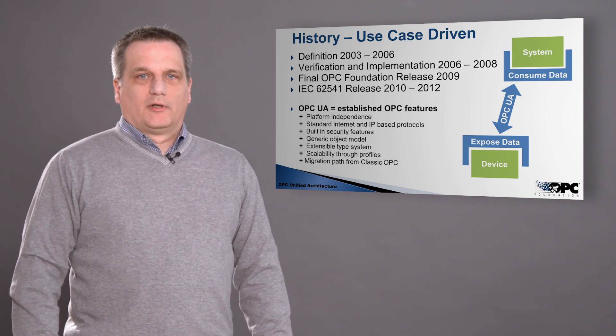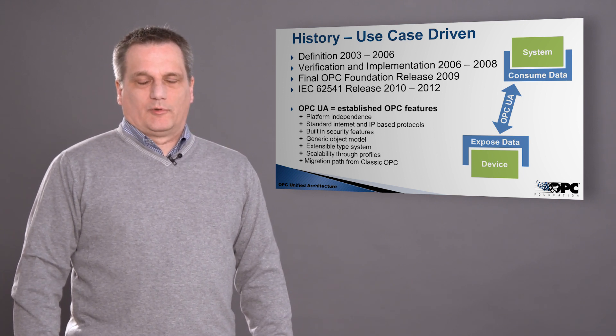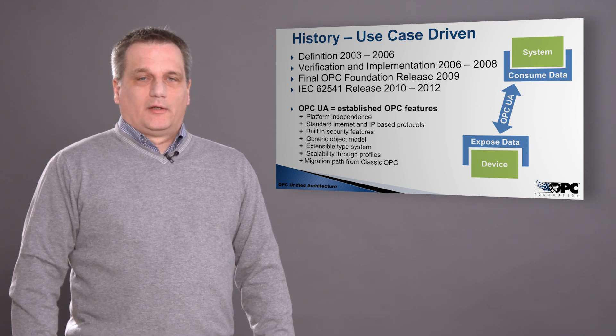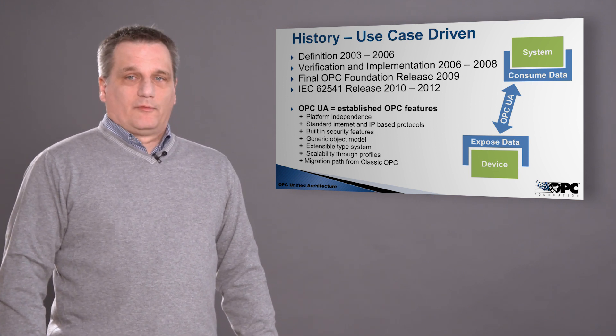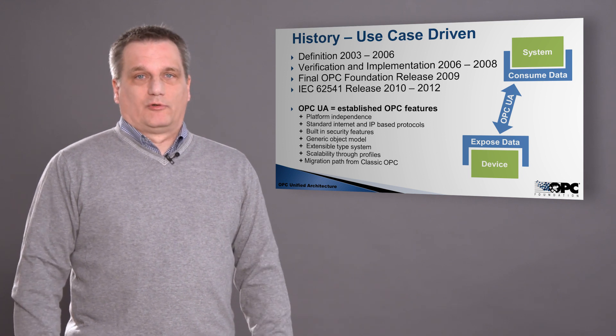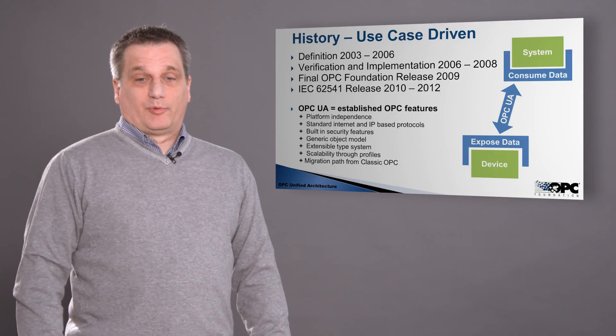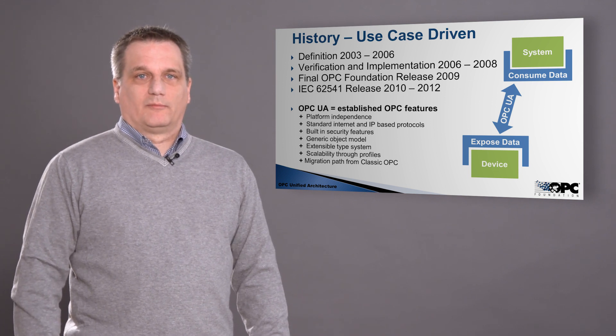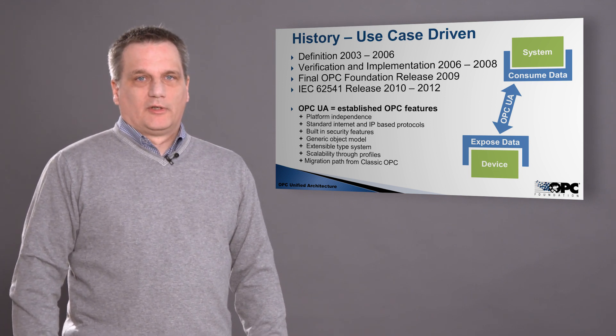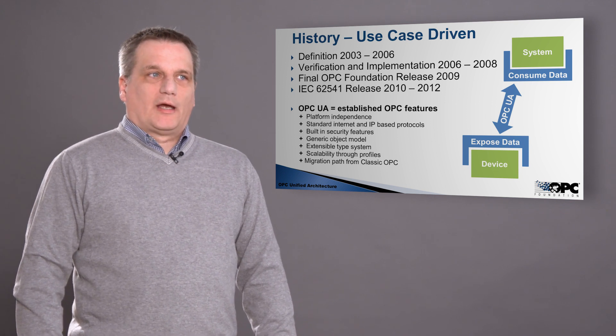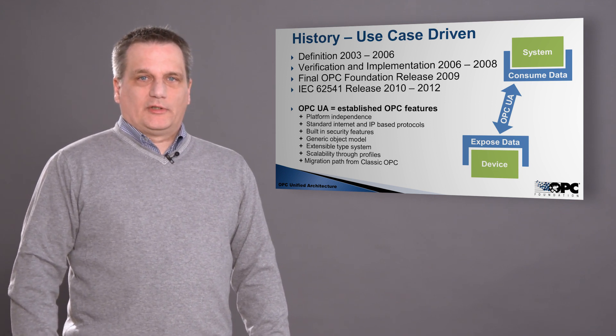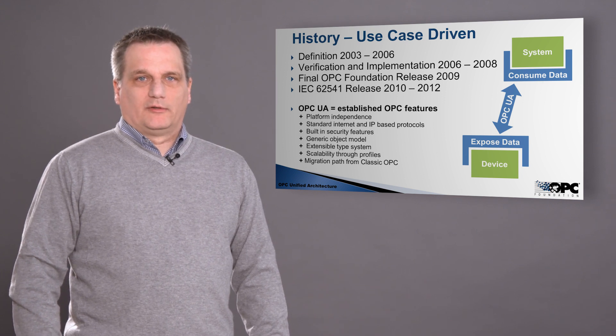OPC UA is the classic OPC feature set plus additional platform independence — you can now implement OPC on any kind of operating system or platform. In addition, we now use standard IP protocols for transporting the information, and we have built-in security features built into the core of OPC, not only for the transport but also for the individual data points in an OPC server, giving us access rights down to a data point level. We also have an extensible type system, which we will talk about in this presentation.